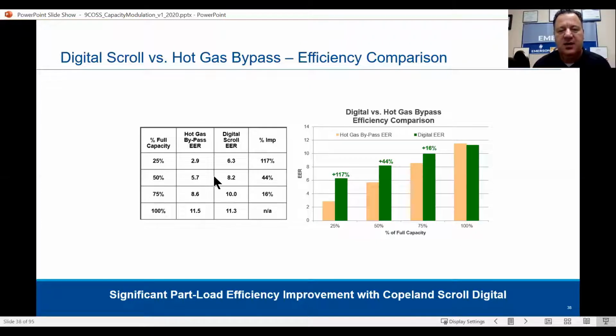And as it goes up, it just keeps getting better until we get to the 75% mark. We're still higher than the hot gas bypass. We're still gaining, but not quite as much as when we first started out. And I'll show you this. Instead of kicking on all that horsepower from a larger compressor, we're ramping that up, if you will. It's not like variable, but I'll show you and explain what I mean by ramping that up. Significant part load efficiency improvement with the Copeland Scroll Digital.